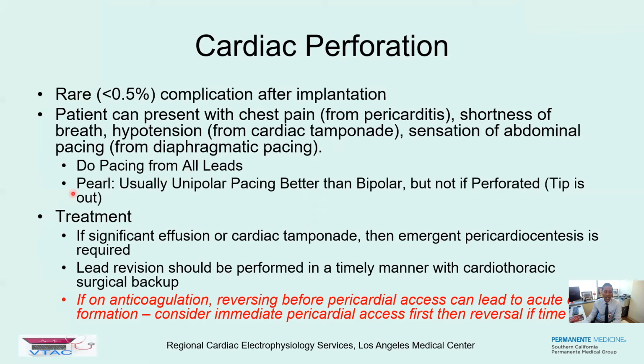One way you can test if there's a perforation, if you're not sure: the thresholds will be up, but you'll learn that pacemaker leads have two poles on them. When there's two poles, usually it captures better from the tip in the heart rather than from the ring. Well, if you pace unipolar from the tip, it's the one scenario where you might find worse thresholds, because that tip is what's sticking out of the heart. So that's a clinical pearl.